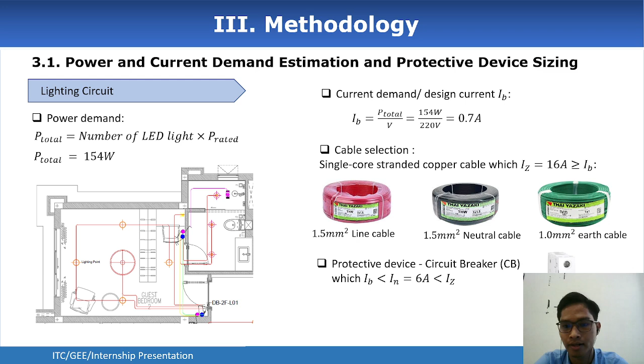For the protective device, use a circuit breaker where the nominal rating current equals 6 amps. Its nominal rating current is greater than the design current but lower than the current carrying capacity of the cable. That means that the circuit breaker must operate when the current demanded by the load is greater than 6 amps, but before the cable is damaged by the overload current.